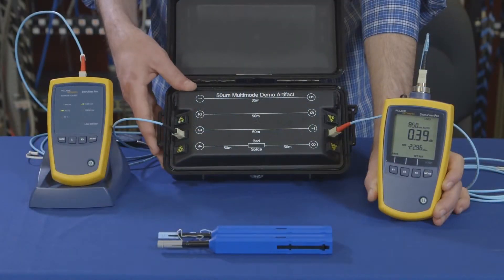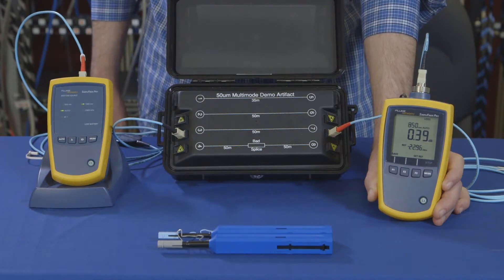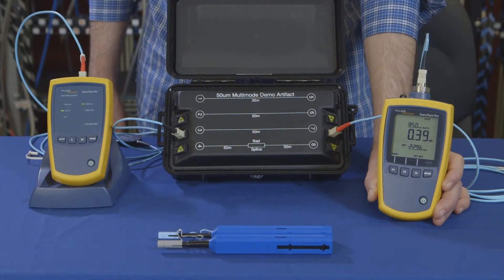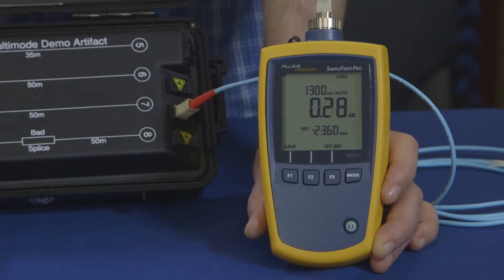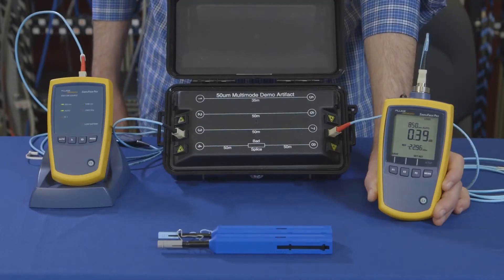After cleaning and inspecting our fiber under test, we connected the light source and the power meter and are ready to take our measurement. You'll notice the source is alternating between 850 and 1300 nanometers, giving you both wavelengths in one result.